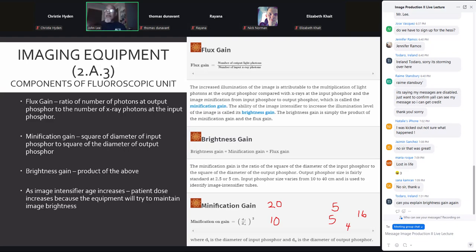So by going into mag mode, using a smaller image intensifier input phosphor size, we're going to decrease our minification gain. So in this system, let's just say that our flux gain here is 100. Again, I'm just pulling numbers out. Our flux gain is 100. Okay? For 20, input phosphor size of 20, our minification gain is 16. 16 times 100, well, that's 1600, right? So when we go into mag mode and switch to 10 for input phosphor size, 10 times 100 is 1,000.